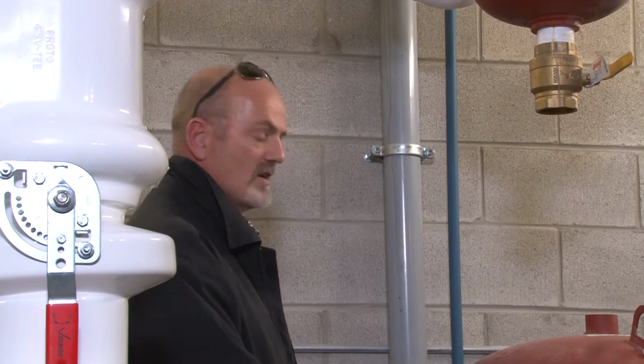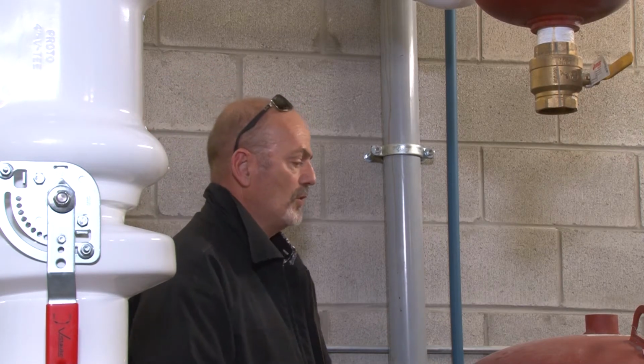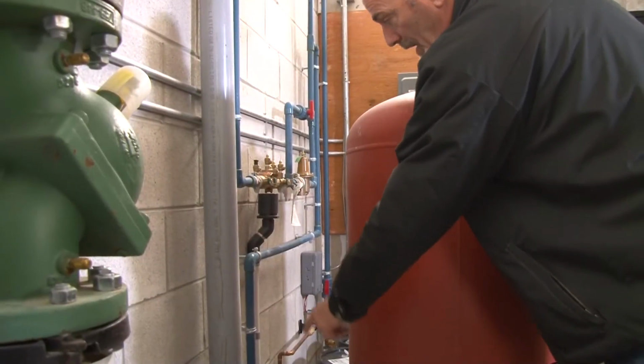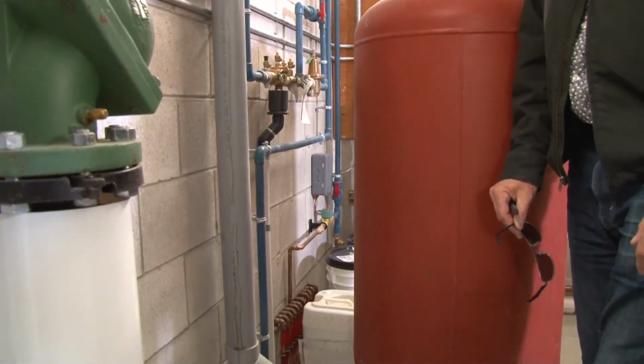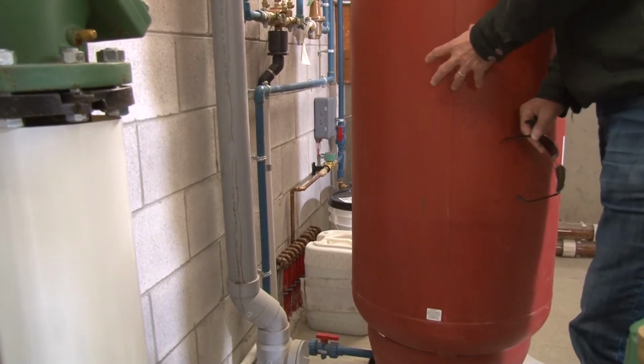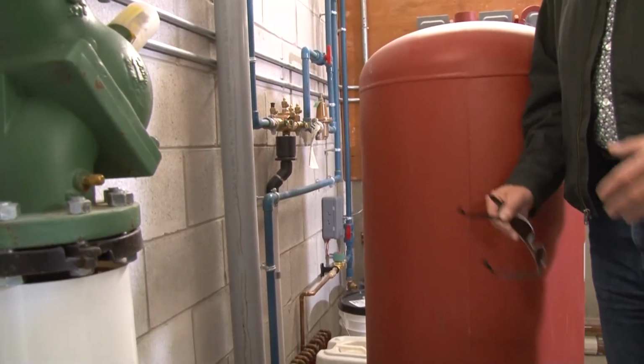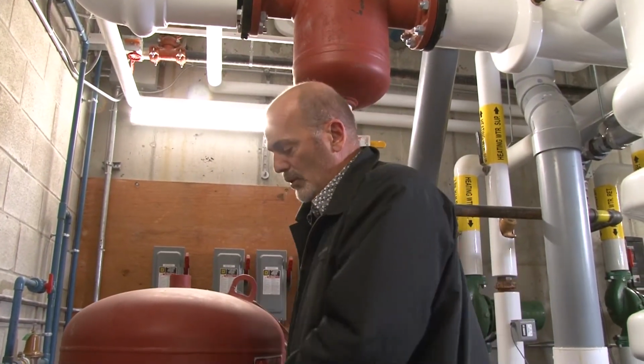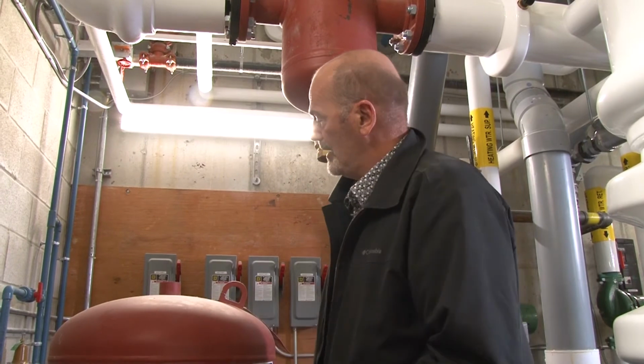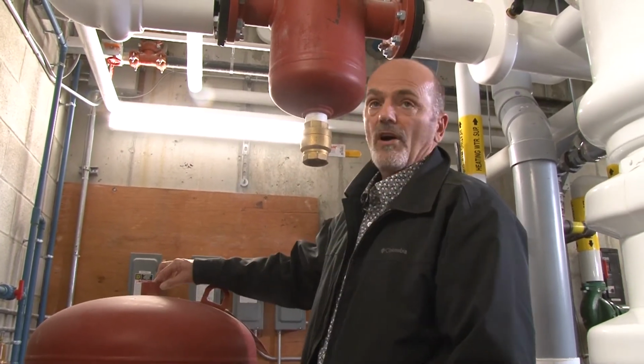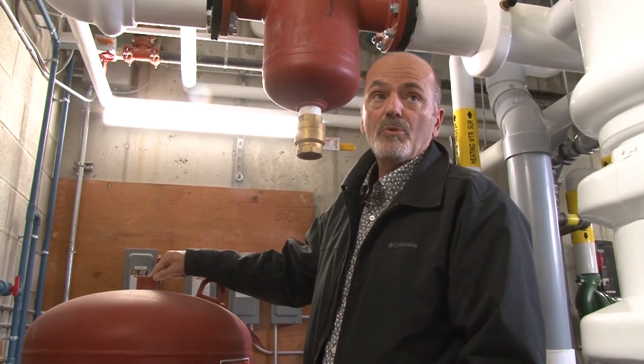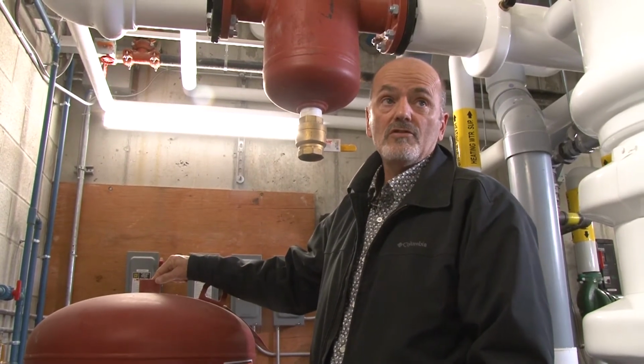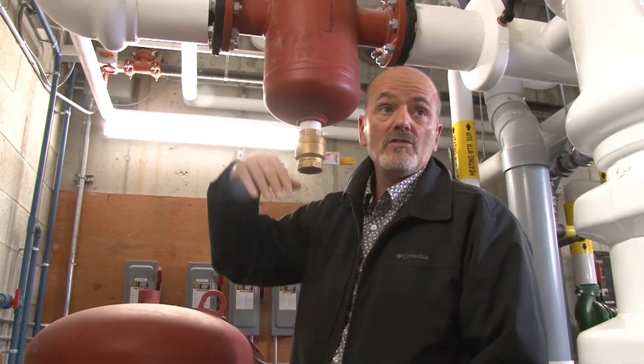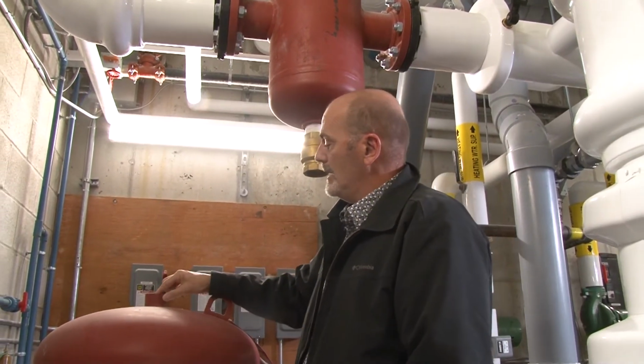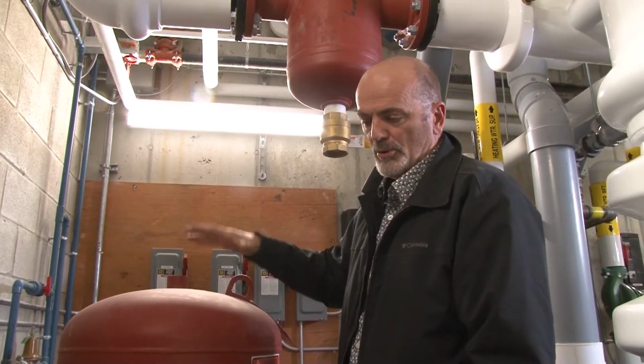So the idea behind an expansion tank is there's a big rubber, for lack of a better word, bladder or balloon inside. And the system fluid is tied into it. This blue pipe is the connection from the system back to the expansion tank. So as that water pressure goes up, it needs to go somewhere because it's expanding. It goes into the bladder in the tank, and on the other side of the bladder, there's an air charge valve on the top of the tank, and the tank comes pre-charged, and then it gets adjusted for site conditions, i.e. how high the building is and how high a water column is above it. It will push the bladder.